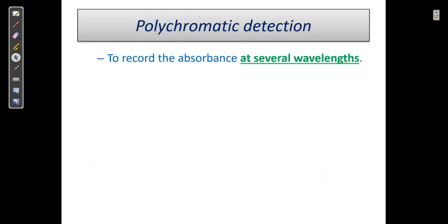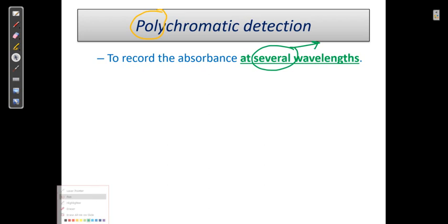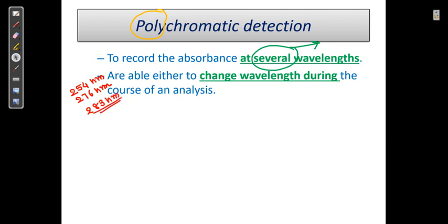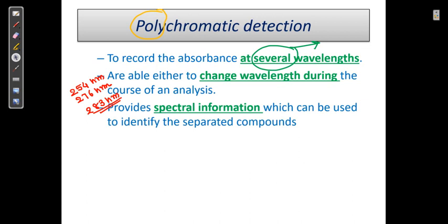Polychromatic detection means detection at several wavelengths simultaneously. There is flexibility to change wavelength — we can analyze and check at 254 nm, 276 nm, and 283 nm, providing a factor of more information.